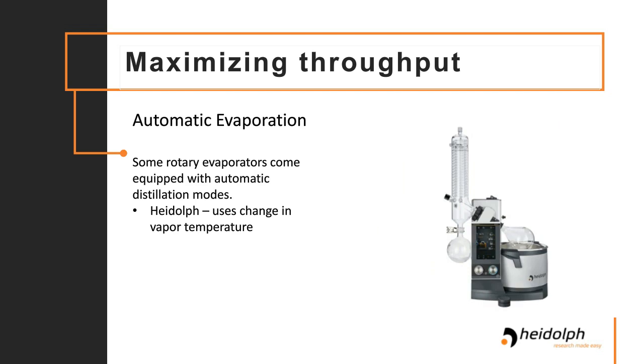Another very nice feature that many of the modern rotary evaporators offer is an automatic evaporation function. This means these systems will find a boiling point automatically. You do not have to gather the data that you need for your specific solvent to find a boiling point. The system is doing that on its own, and you don't have that much effort. Another advantage is that the very modern systems have a very balanced and very sensitive way to find a boiling point, so it also prevents foaming and bumping.